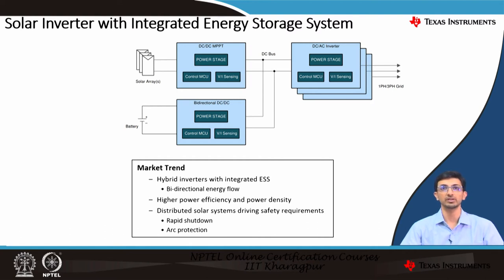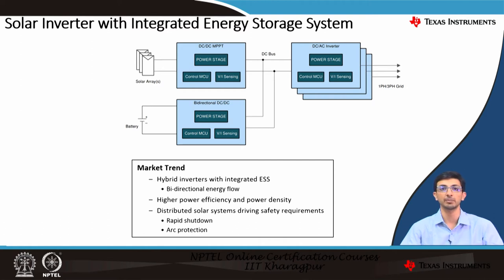The second application is the solar inverter with integrated energy storage system. The solar arrays are connected to the DC-DC stage with maximum power point tracking (MPPT), which ultimately feeds into the DC-AC inverter stage. We also require an integrated energy storage system — a battery pack — with a bi-directional DC-DC stage connected to the DC bus. The market trend here is a hybrid inverter with integrated ESS (energy storage system). This also requires bi-directional energy flow and demands high power efficiency and power density.